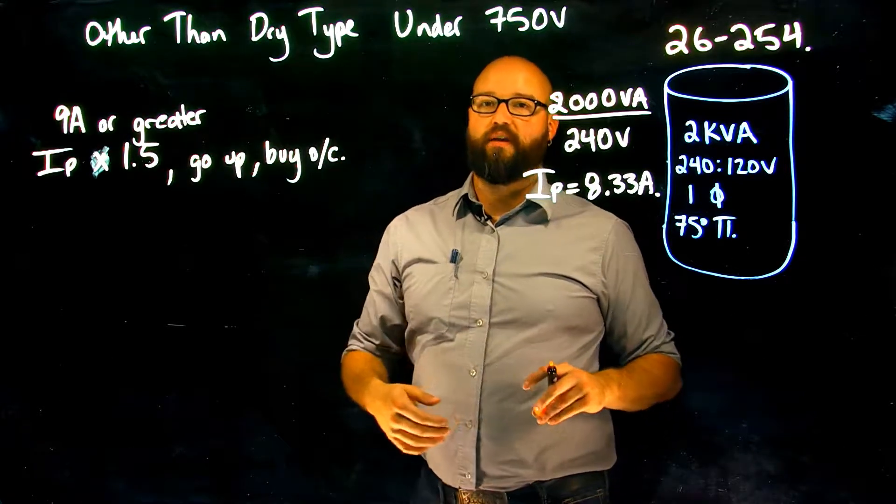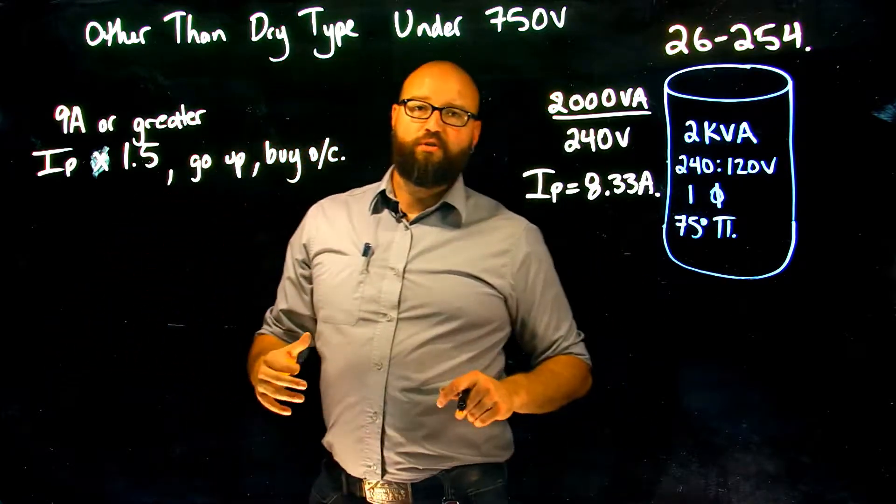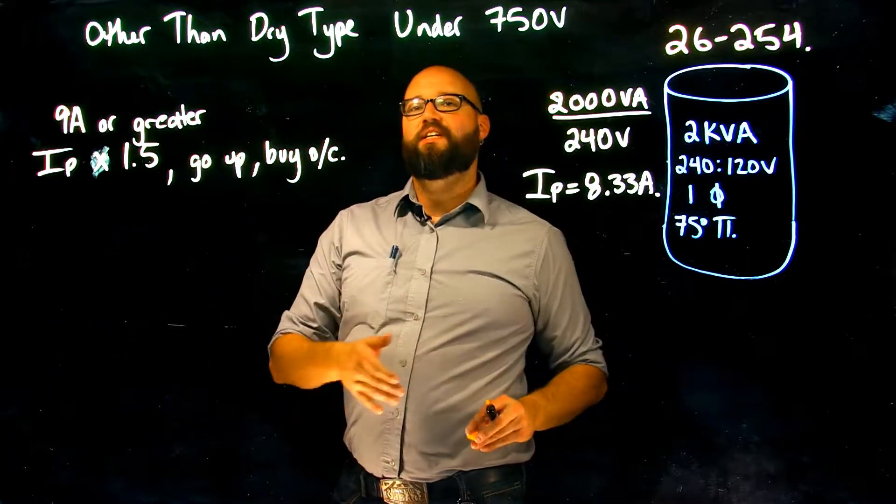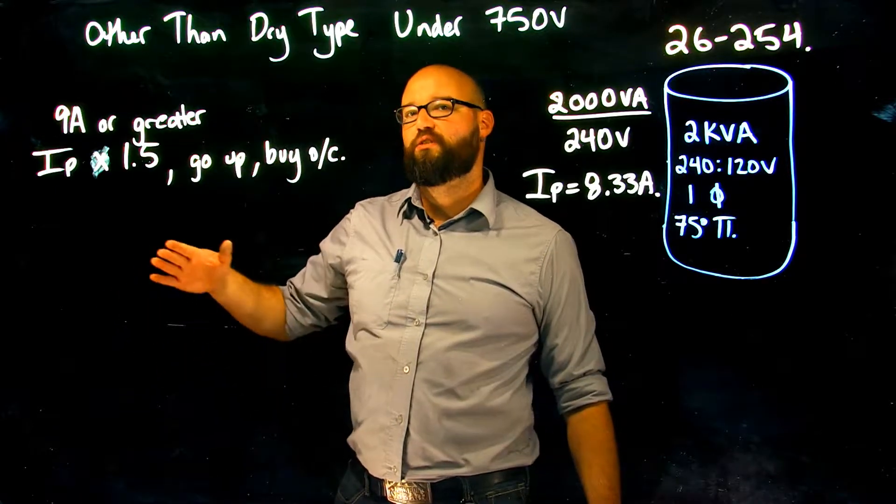So if this number was over 9 amps we would multiply it by 1.5, we would go up and choose the next available size overcurrent. Sub rule 2 item b tells me if it is less than 9 amps.